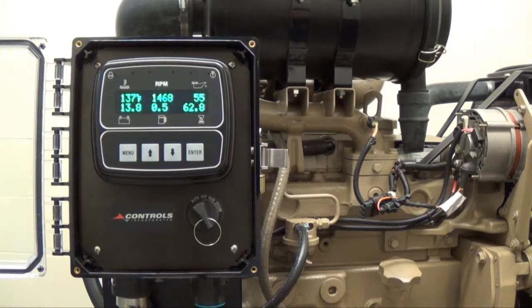If the level of fluid in the well falls below the target height of 300 inches, the engine will begin to decelerate to the minimum control speed of 800 RPM so that the well can fill back up to the target level. The pump will continue to operate in this pattern, ramping up and down, in order to maintain a fluid level of 300 inches. The closer the level gets to 300 inches, the smaller the adjustments are in engine speed.